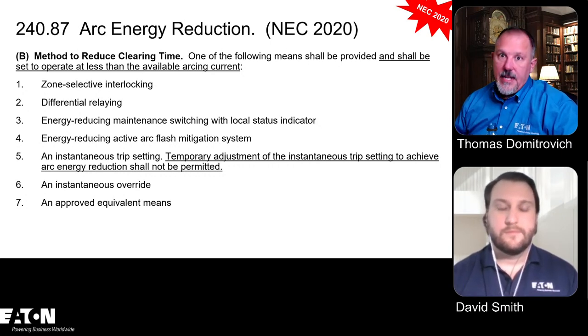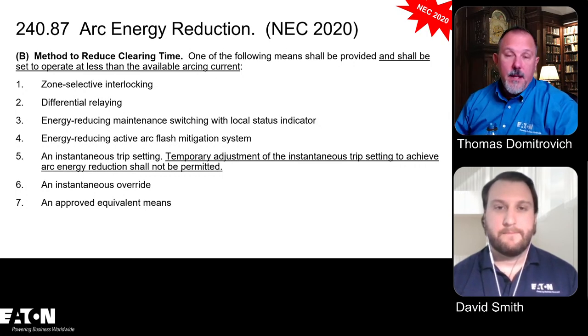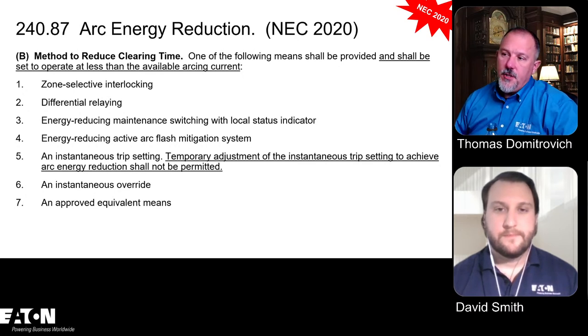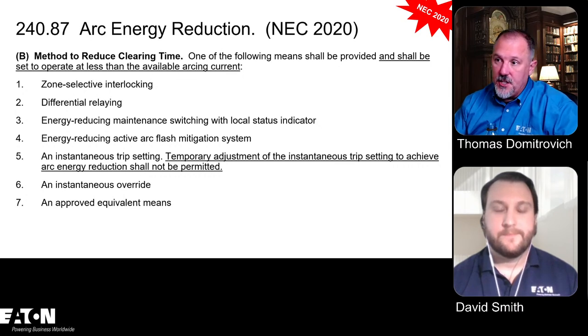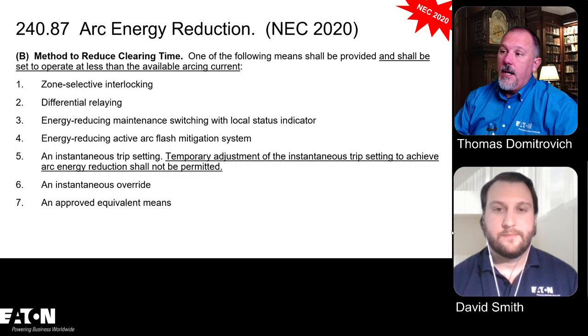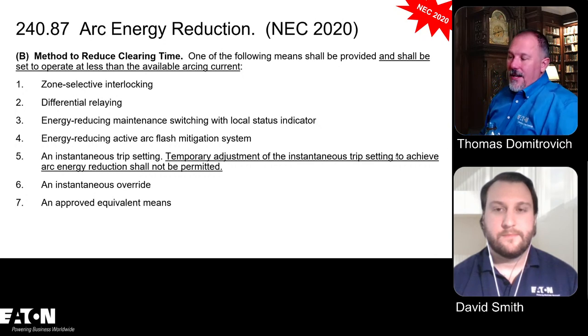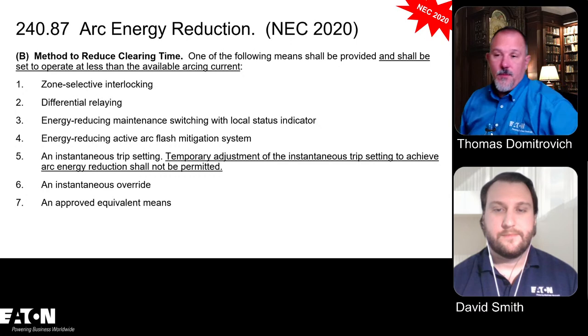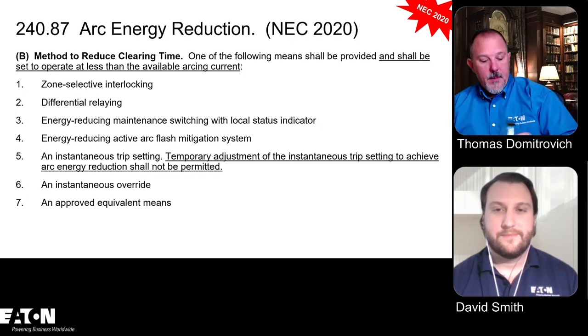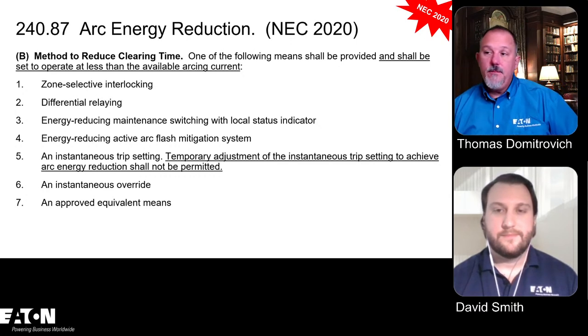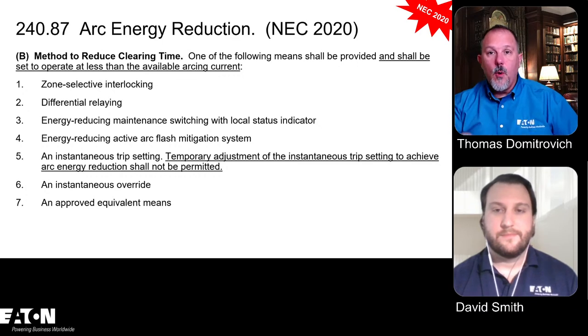Doesn't mean you don't see it ever on a 480 volt system or a 600 volt system, but much rarer. Energy reducing maintenance switch with a local status indicator and the active arc flash mitigation systems. Obviously, you have your instantaneous trip. We added this language that you cannot temporarily adjust. So what we learned was some people were saying, hey, I'm just going to roll down the instantaneous when I work and roll it back up again.